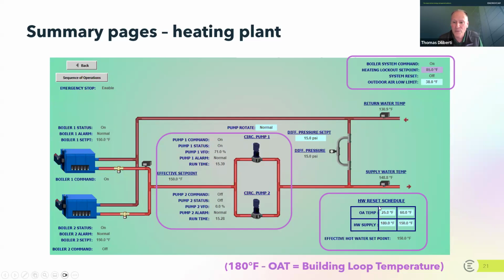This whole concept of a reset schedule is in order to allow you to take advantage of times when there's not the heating demand need. So again, take advantage of this. I circled these pumps here to highlight this: many times, and it's even shown in the picture here, I would describe this as redundant pumping. There are two pumps here because if one fails, you don't lose the system. So these two pumps are in a position, the piping, it could go up or it could go down in order to get out to the building.